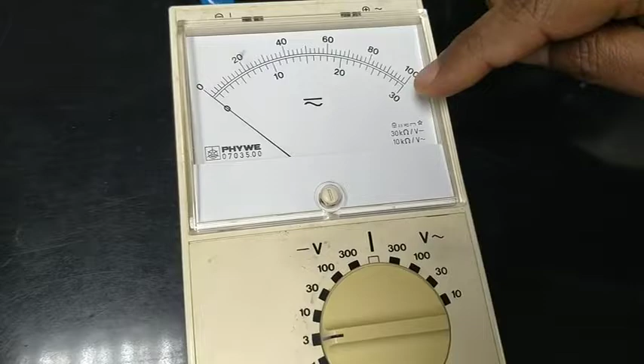If I am using the 1, then I will be using the upper scale and dividing everything by 100, because the maximum will always be 100. So whenever you use 1, 10, 100, you will be using the upper scale, and whenever you use anything that contains a 3, so 0.3, 3 or 30, you will be using the lower scale, and the maximum will be equal to the value that is given there. So this is 3 now, it means maximum will be equal to 3. So this will be 2, this will be 1, and for every division, of course, you can see how much it will be.